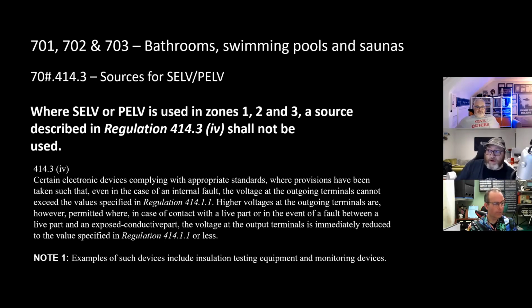Higher voltages at the outgoing terminals are, however, allowed in the case of contact with a live part or in the event of a fault between live parts and exposed conductive parts. This, I think, is why they're going, oh, we don't like that when we have the presence of water. So they don't allow this exception as a source of SELV because I think of that second half there, where this method would allow a higher voltage to occur. So this one mention of a source for SELV has been excluded from those 3 special locations.